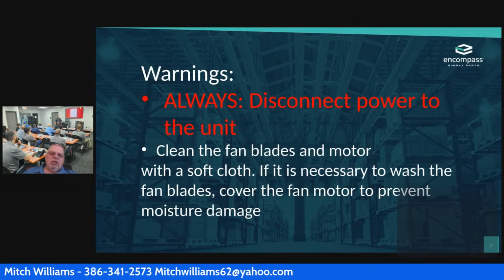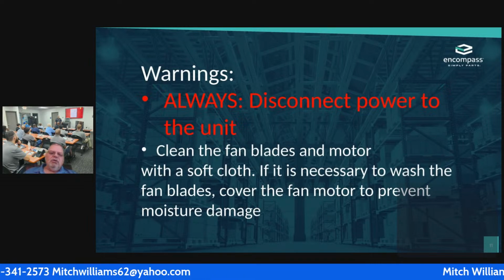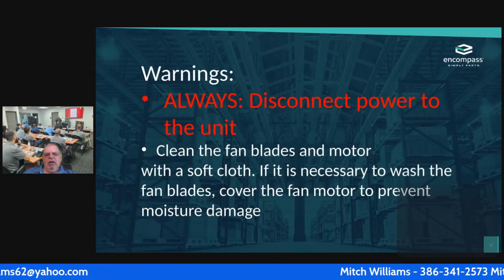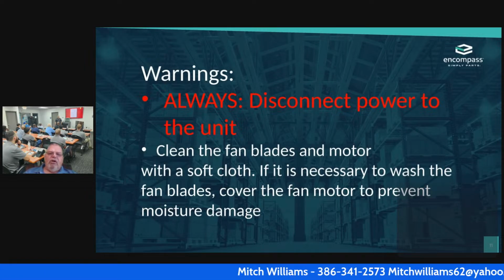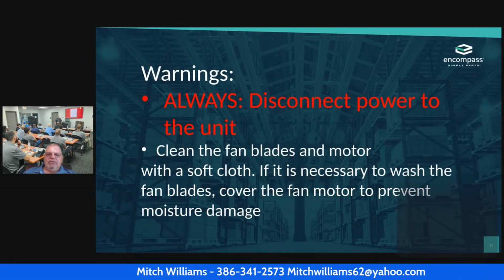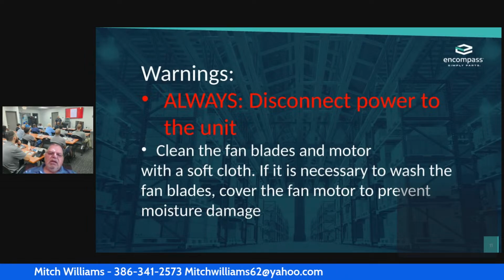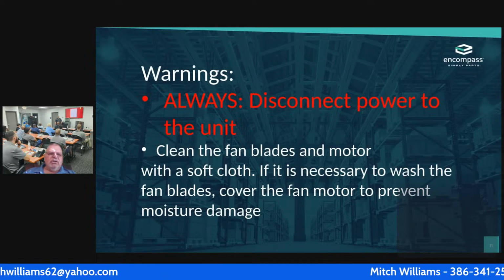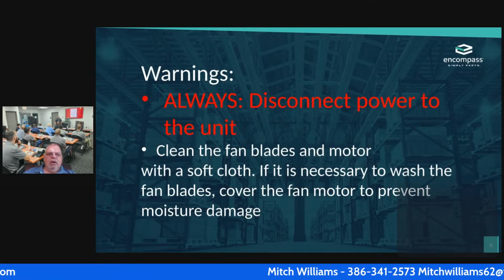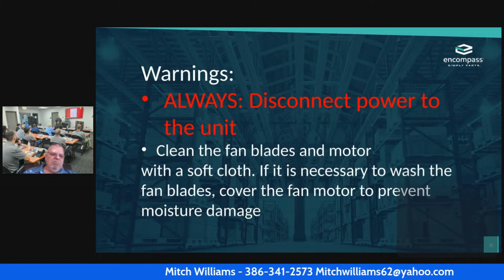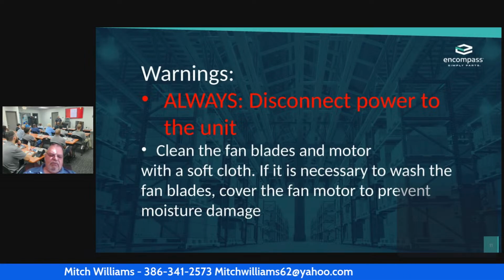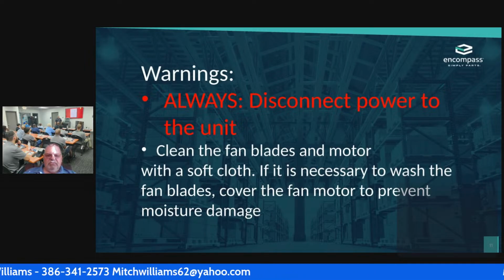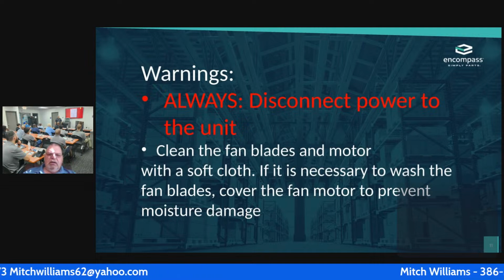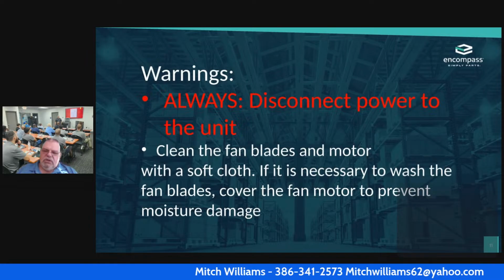If I'm going to clean the fan blades or the motor, I'm going to do that with a soft cloth. If it's necessary to wash the fan blades, cover the fan motor to prevent moisture damage. That just goes without saying. On many of these mini units, they do not have the ability. If I'm spraying water on it, it'll get into the fan motor and it will cause an issue.